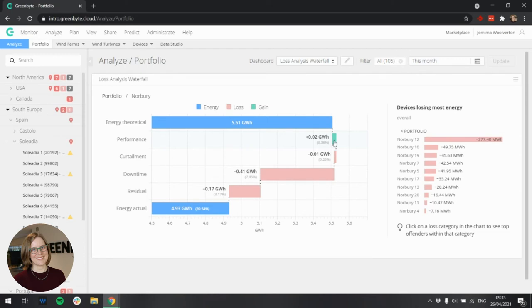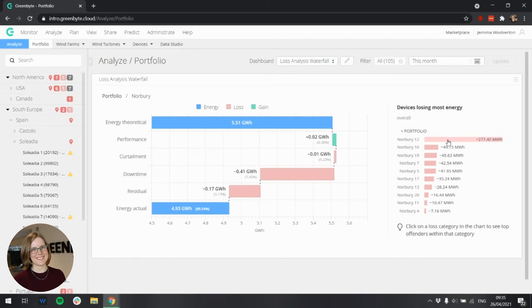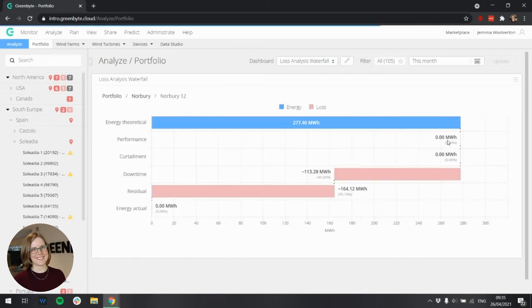If I want to find out which devices are losing most energy, I can look in the top offenders. Here it shows that Norbury 12 is losing most energy, and if I want to find out about the individual losses for that device, I can click on it. And here I can see exactly which losses are recorded for this device.